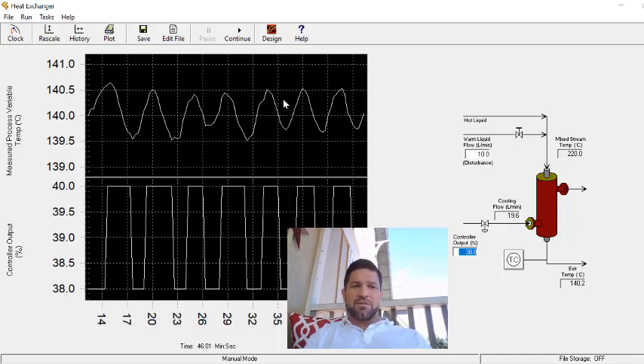I just want to note because we're talking about the derivative term. One of the things that will be important to look at is how much your controller is changing. It's really important that you don't have your controller changing too rapidly or swinging wide open and entirely closed. Because that will both degrade your performance and also degrade the hardware that's operating on your system.